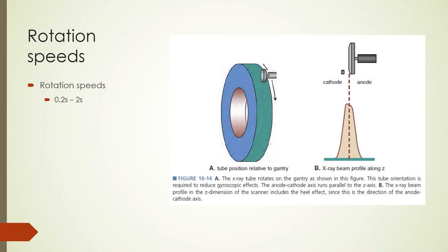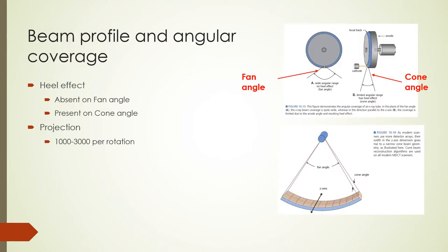The design of the gantry and X-ray tube reduces wobbling that would add significant torque to the scanner. The X-ray beam profile has the anode-cathode axis running parallel with the Z-axis of the scanner. X-ray angular coverage is defined by the fan angle and cone angle. Most scanners have a 60-degree fan angle; the cone angle is much smaller. The heel effect is absent along the fan angle but is present on the cone angle.